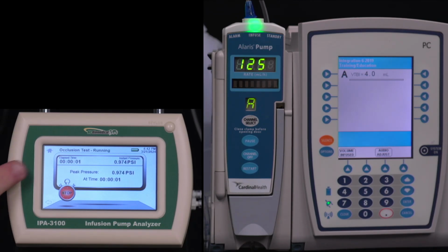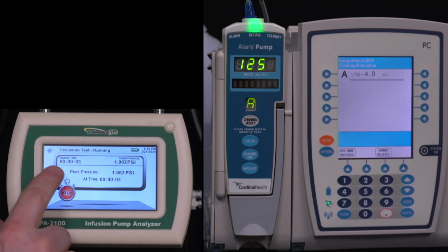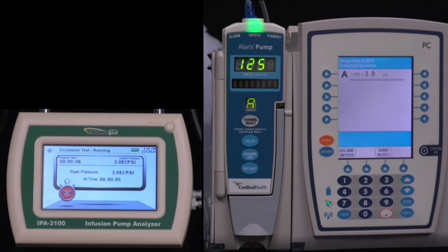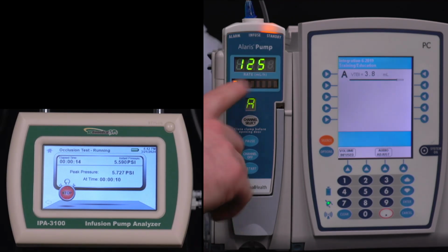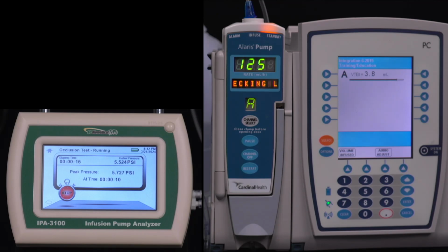And now the pressure has started to rise and the time automatically started. It's keeping track of the peak pressure, and it's telling me, checking the line. So the pump detected that there was pressure, occlusion downstream. It's going to wait a few seconds, and then it's going to throw an alarm.